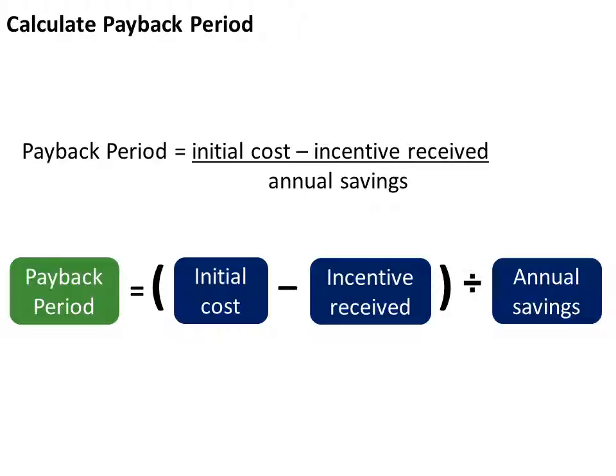The formula for calculating the payback for an energy efficiency project is initial cost minus incentive received divided by annual savings. This formula is on the formulas to calculate payback guide located on the webpage where you access this course. This guide also contains all of the formulas we'll go over today.